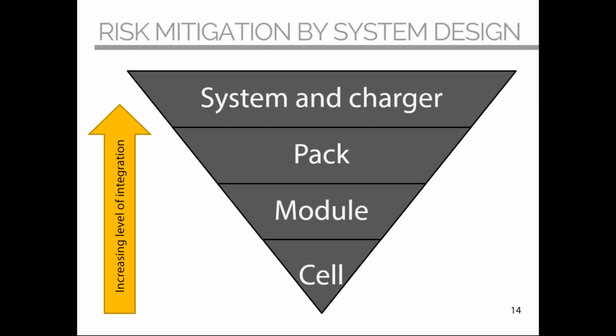There are real risks to lithium-ion, but they can be mitigated by proper system design. There's no rocket science here. It's fairly straightforward, well understood system design principles. A safe design starts from the bottom up. So I've got an inverted pyramid here to show that you build in safety from the lowest level of assembly, which is the cell, and you cascade up to the higher levels of integration. So cells are built into modules, modules are built into a pack. The pack is wrapped in a case, integrated with a system, including battery management and cooling and a charger. And at each level, you consider safety, you consider the impact of single points of failure. Let's walk through this step by step.